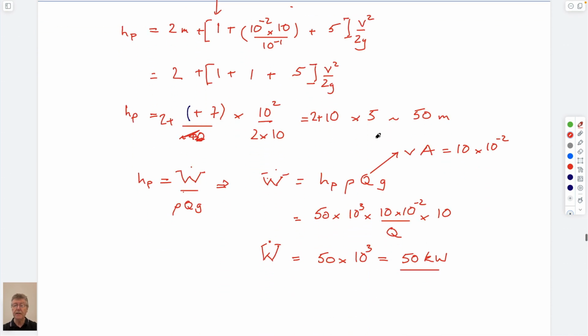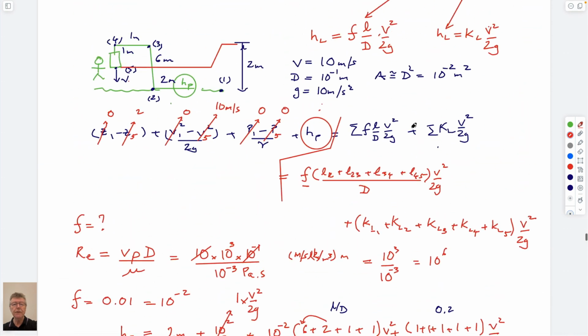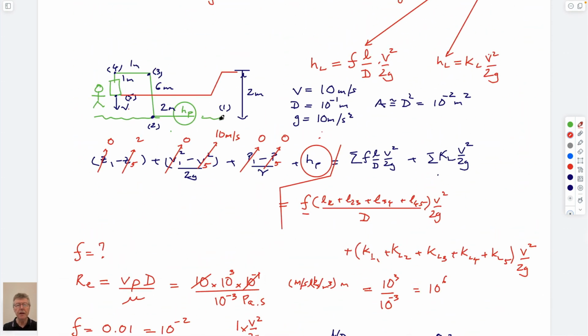And if you do that, it comes out to be something like 50 meters. You'd think if you're pumping up 2 meters, the head you'd need would be at least 2 meters if it's a perfect system—you should have a feel for these things. If you're pumping from 0 elevation up to 2 meters above, with that distance being 2 meters, the pump in a perfect system with no head losses would need to supply at least 2 meters to get it up there. That's what that really means.